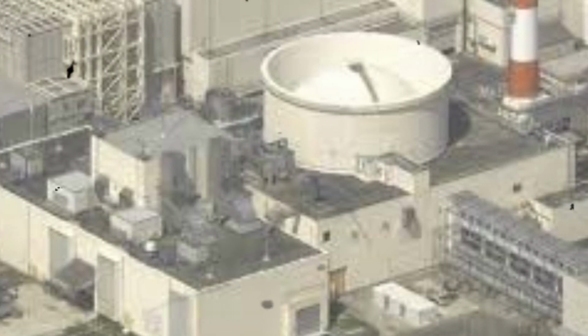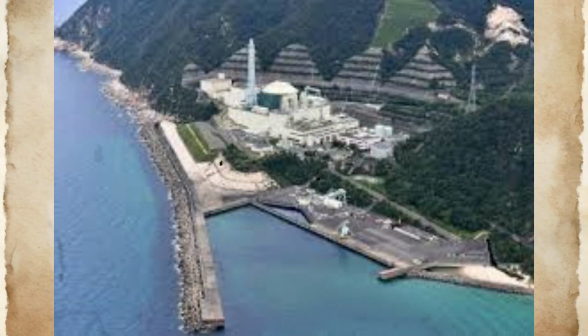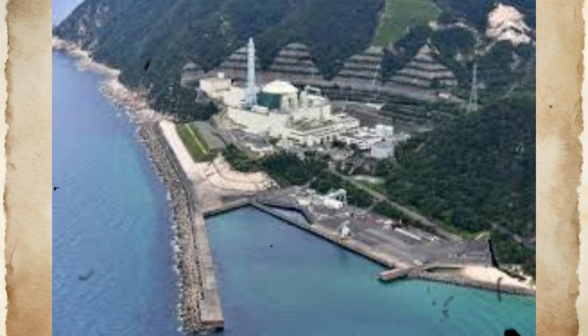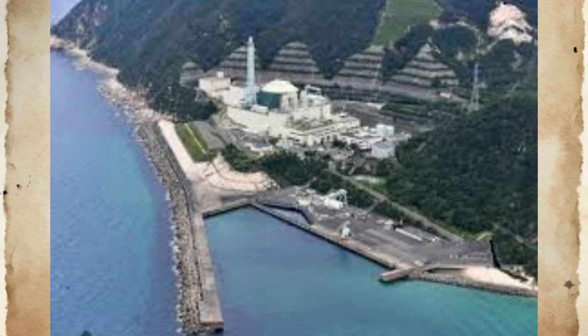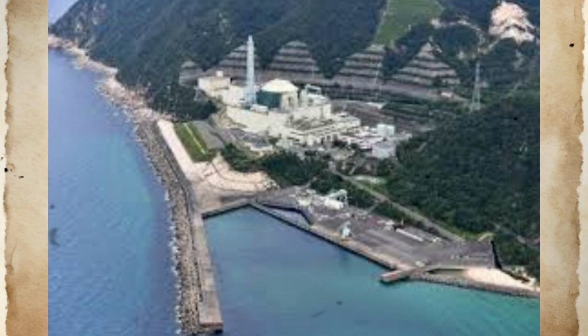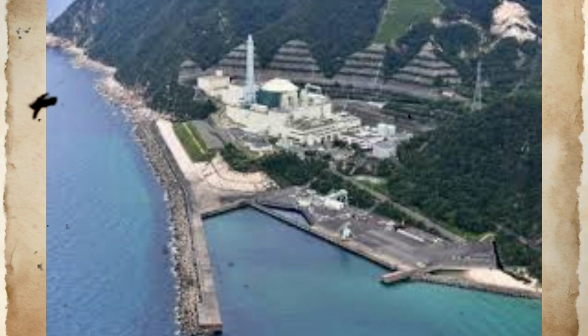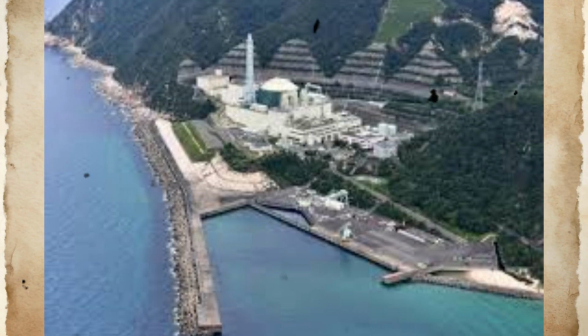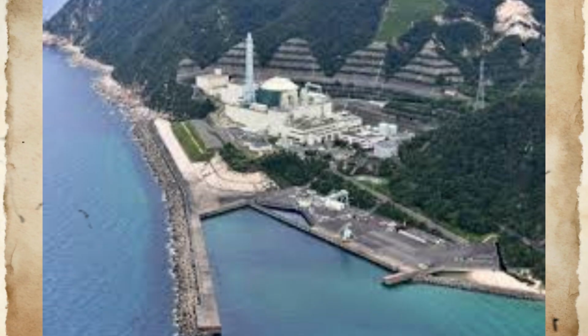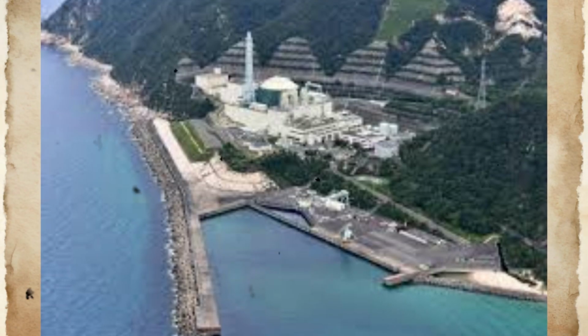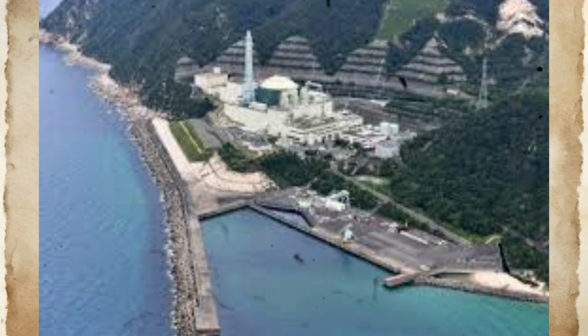Flow-induced vibration analysis conducted after the incident revealed that the well tube experienced symmetric vortex shedding at the operating sodium flow rate of 5 meters per second. The sharp taper geometry created flow separation that generated alternating vortices on both sides of the well, producing oscillating forces in multiple directions simultaneously. Unlike resonant vibrations that create large amplitude oscillations at specific frequencies, the vortex shedding produced small amplitude vibrations across a range of frequencies that accumulated fatigue damage over extended operating periods.